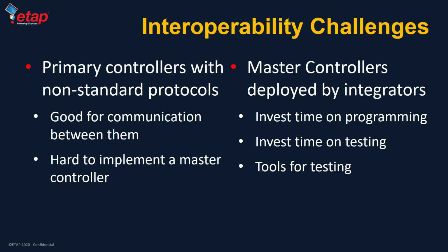The challenge becomes having the capability to communicate to all different types of controllers and devices. Many primary controllers in the market support proprietary protocols designed to communicate to the same brand of device. Communication between the same brand of device is relatively simple to configure, but it ties you down to the limitations of the functionality presented. As the manufacturers of different sources provide you with their own primary controllers, implementing a controller with limited communication options make it close to impossible to implement.